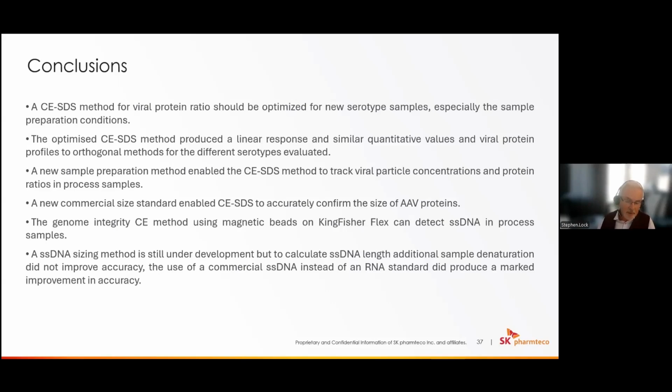the year. And finally, I think this is an important area that I personally wanted to test as well, which is to improve the sizing, specifically of single-stranded DNA in this AAV viral vector. Historically at SCIEX, we've managed to get good sizing when we've compared and looked at RNA genome material with an RNA ladder, but we always found that when we used the RNA ladder for single-stranded DNA, our sizing wasn't very accurate. And by moving to a single-stranded DNA ladder instead of an RNA ladder, we've really improved the accuracy of our sizing as well. We're not quite there yet.